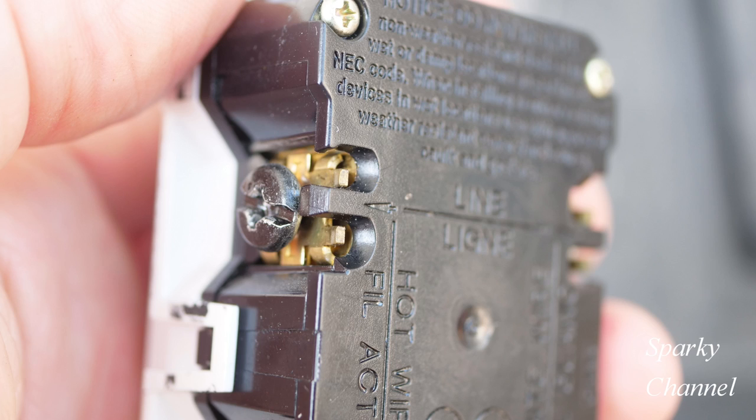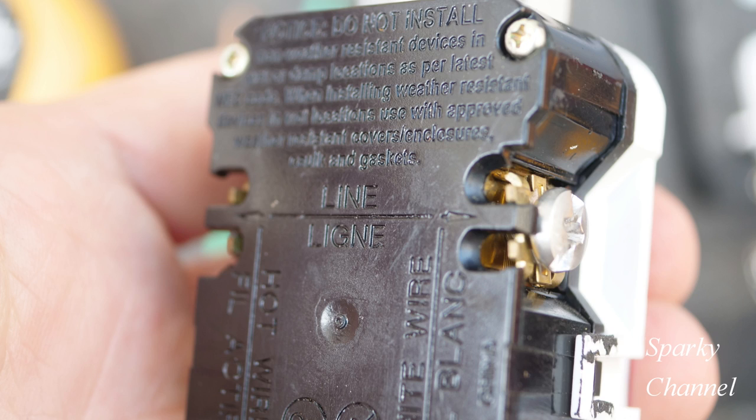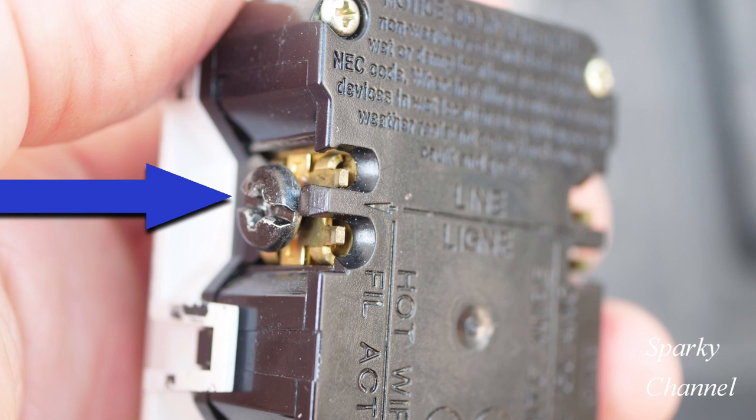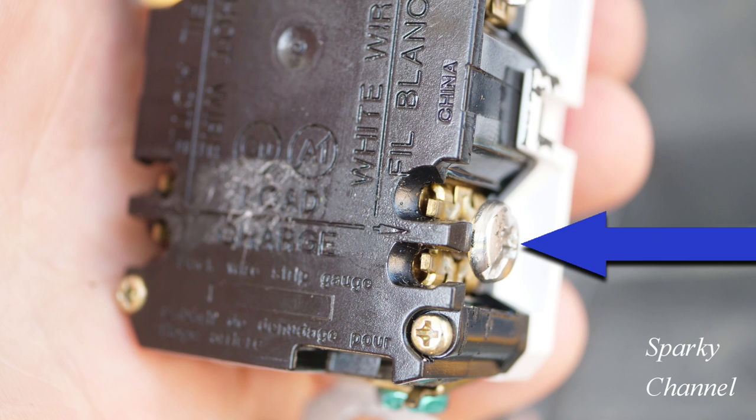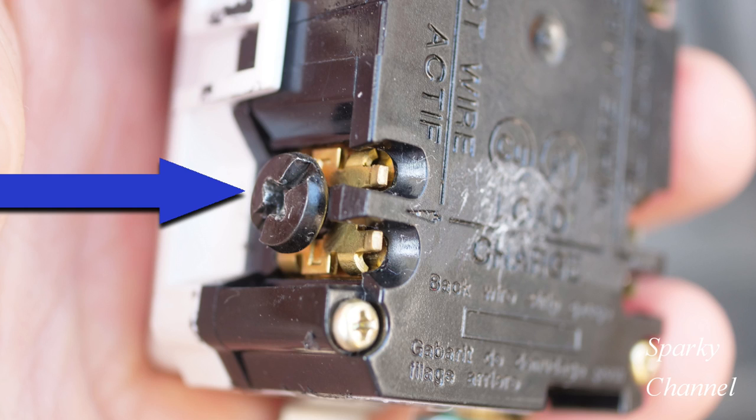On the GFCI receptacle you will find a line area, which is for the line wires. The line wires are the ones that provide the power from the circuit to the receptacles. The neutral line wire goes to the silver terminal and the black hot wire goes to the brass terminal. Also on the GFCI you will find a load area. The load wires bring power in a protected manner to the adjacent standard receptacle. I'll accomplish this using a white pigtail for the neutral and a black pigtail for the hot, from the load to the adjacent standard receptacle.